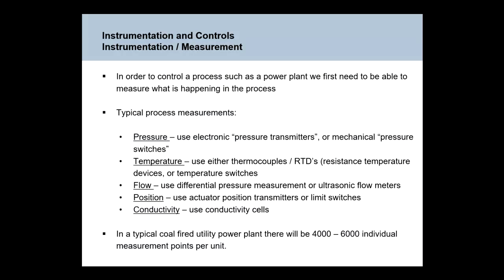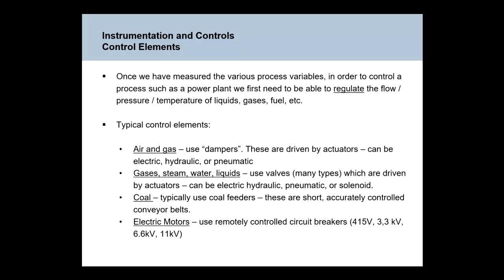So there will be, on a typical coal-fired power plant, between 4,000 and 6,000 measurement devices, things this size, that are measuring temperature, pressure, flow, conductivity, and so on. Okay? And then you need to control the flow of oil, fuel, water, hydrogen, whatever it is. So you have devices called control elements that are valves, dampers, circuit breakers that will control all of those things. And that allows you to start and run your power plant remotely from your control room.